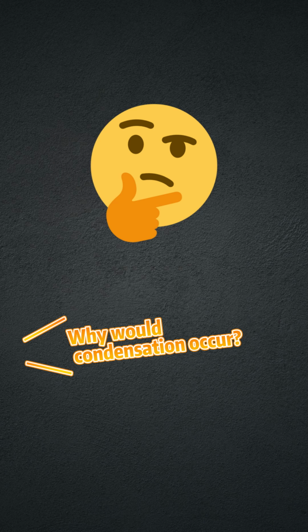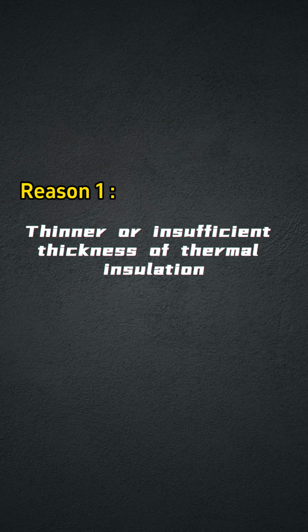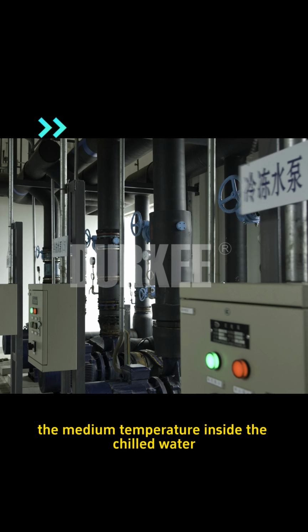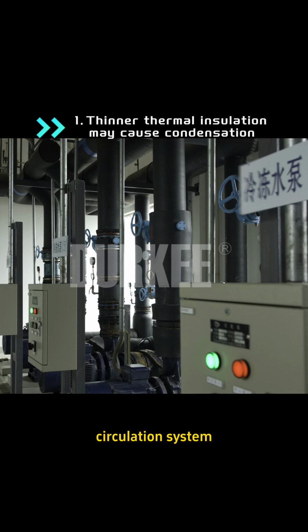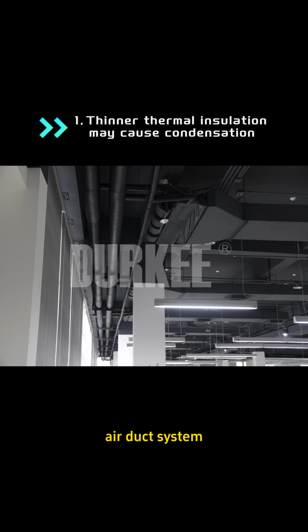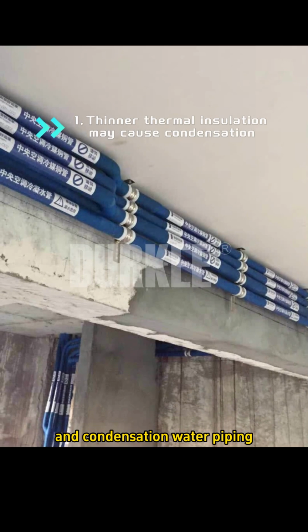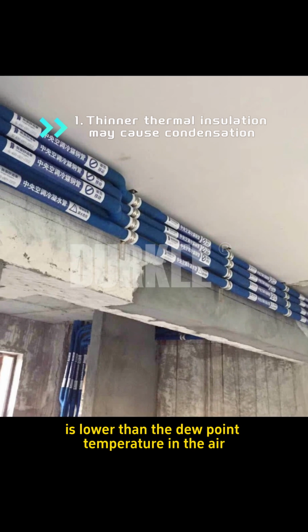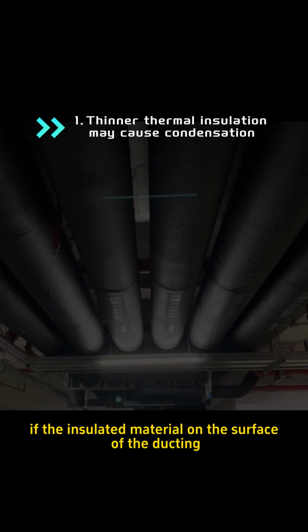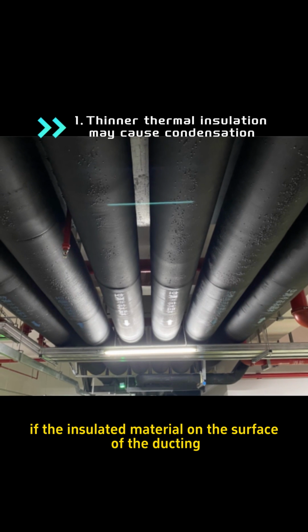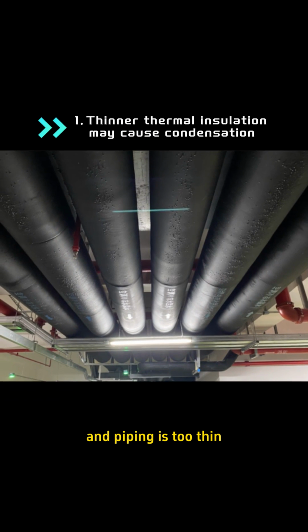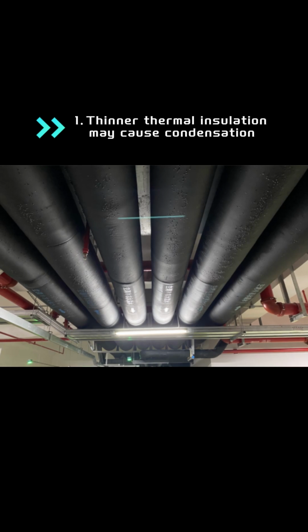Why would condensation occur? Reason 1. Thinner or insufficient thickness of thermal insulation. The medium temperature inside the chilled water circulation system, air duct system, and condensation water piping is lower than the dew point temperature in the air. If the insulated material on the surface of the ducting and piping is too thin, then condensation will occur.